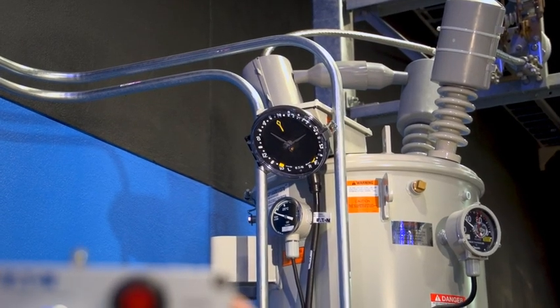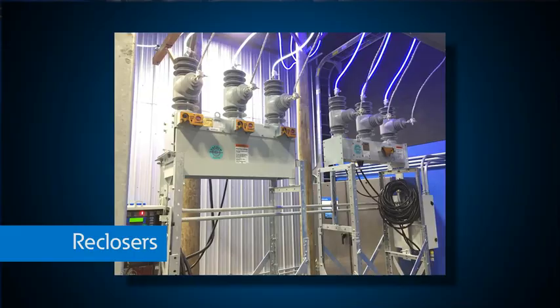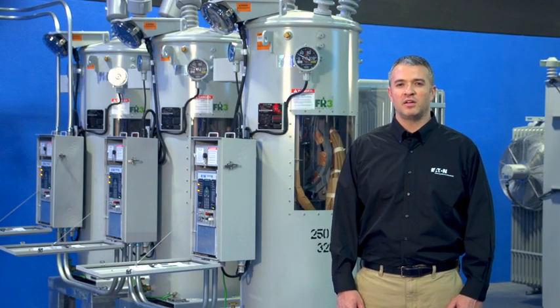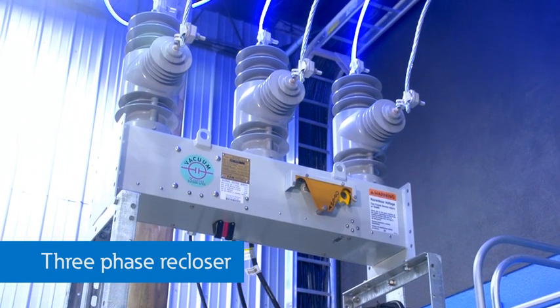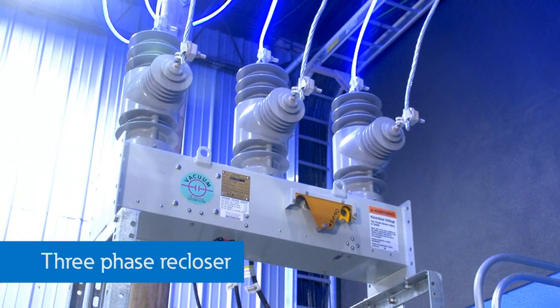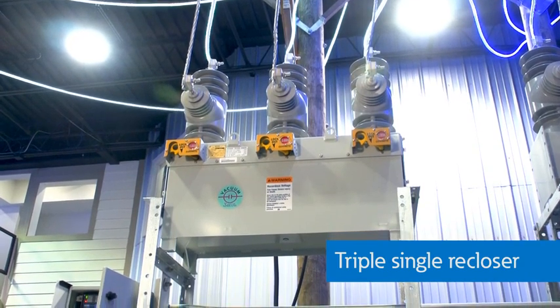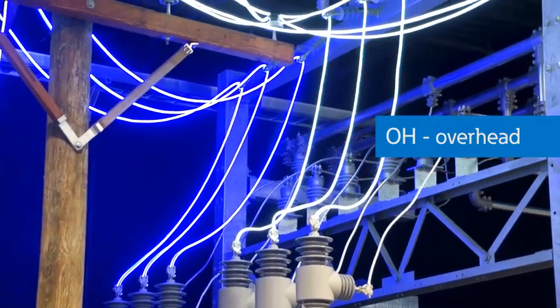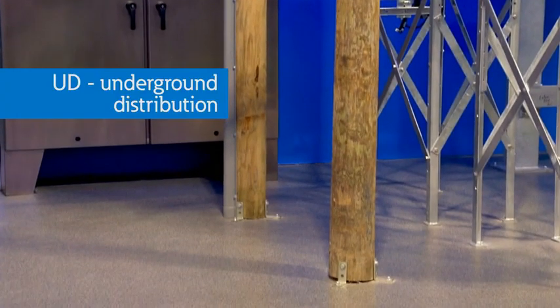Notice that they are partially rated because they are only 10% of the required load that they serve. From the regulators, these two reclosers feed the two main feeders coming out of this substation. This recloser is called a three-phase recloser because it will clear all three phases during a downstream fault, and this one is called a triple-single because it can operate independently on each phase during fault conditions. The 13.8 kV feeders from these two reclosers then feed overhead and underground medium voltage distribution circuits.